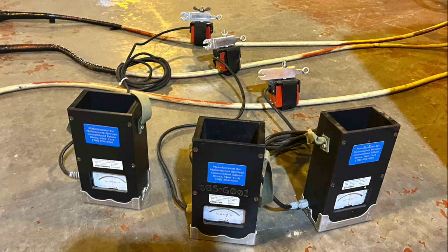A multiple galvanometer method is another way to perform this job function. If you're fortunate enough to have 3 galvanometers in your station, you can place 3 separate galvanometers on each phase, while the test set is off and the feeder is grounded. You will then turn on the high voltage set, and open the ground breaker. Once you have the correct value and duration as per your operating order, you can then check the gauges on the galvanometers from a safe distance. In this scenario you are able to check all 3 galvanometers at the same time.